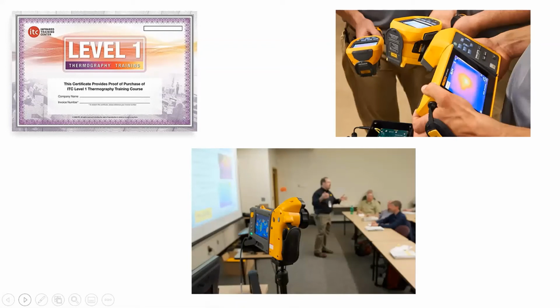These classes are tough. I've actually been to a facility where they purchased a camera, and their facility maintenance guys tried using it themselves. They took some images and found a loose lug on an air handler showing a hot spot. The guy went in, shut it down, torqued it at night, and snapped the bolt right off.